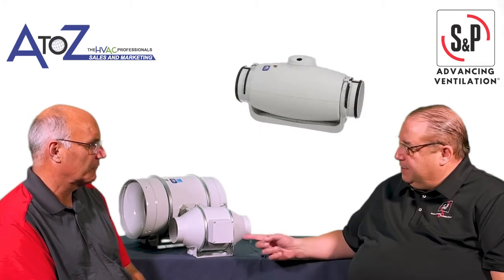You need a booster fan. A lot of those VRF units might accept outside air, but they won't draw it in. There's no way to force it in there. So you're going to need an inline fan like this to push the proper amount of outside air into that VRF fan coil, into the return air, or if it's a ceiling cassette unit, there's a spot to duct it right in. So if you envision every classroom and every place getting more outside air than they have in the past, this is the way to do it.